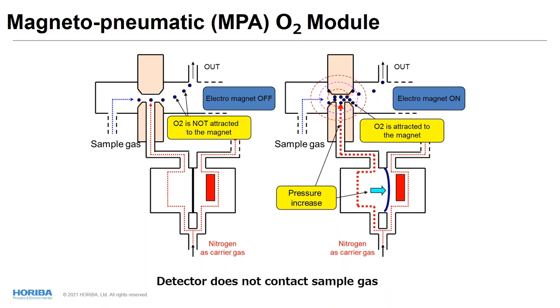And there is an electromagnet, and while it is off, O2 is not attracted to the magnet. In this chamber, we feed a carrier gas from this area, which will be nitrogen as the carrier gas. So while the electromagnet is off, the sample and the carrier gas flow smoothly, right? Because there are no changes in pressure or flow. Then see the picture on the right side: when the electromagnet is on, O2 starts being attracted to the magnet. So as you can see, it's a very busy area with the O2 molecules.